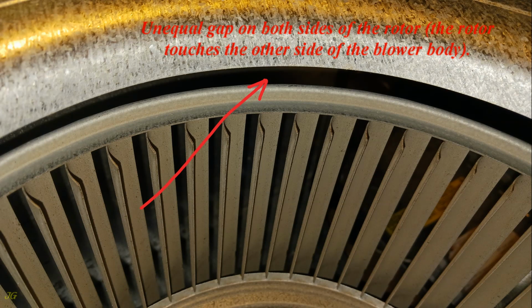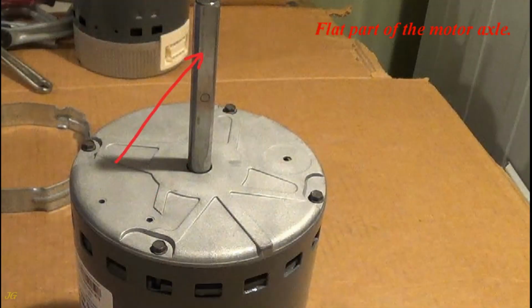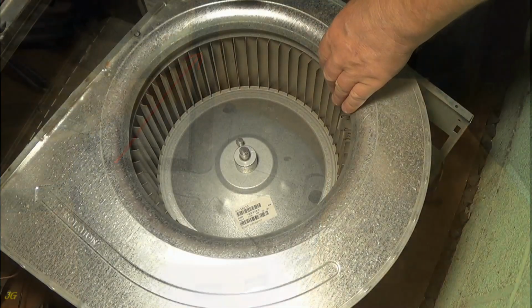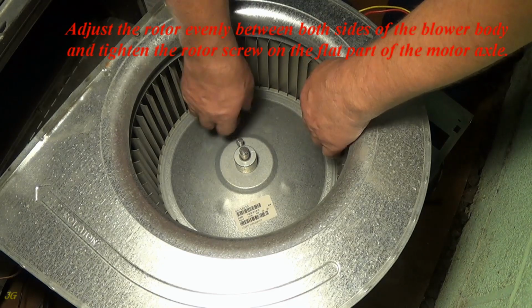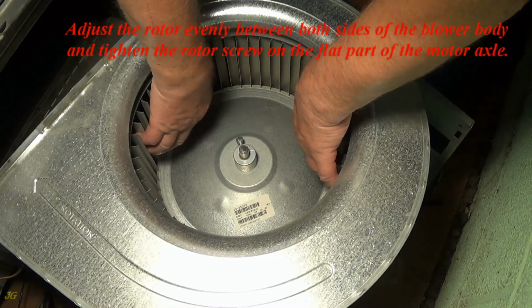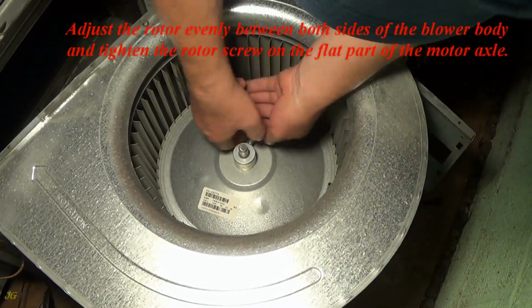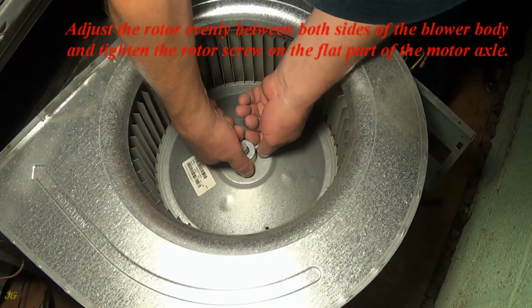Unequal gap on both sides of the rotor. The rotor touches the other side of the blower body. Flat part of the motor axle. Adjust the rotor evenly between both sides of the blower body and tighten the rotor screw on the flat part of the motor axle.